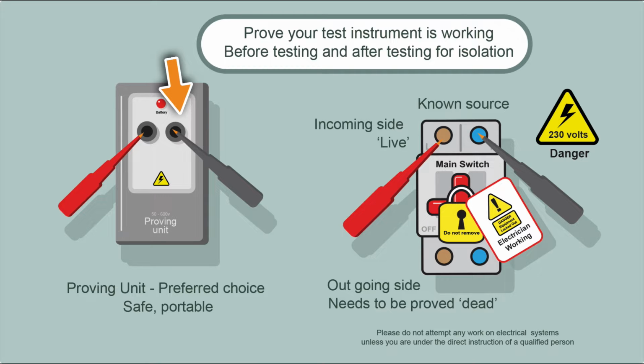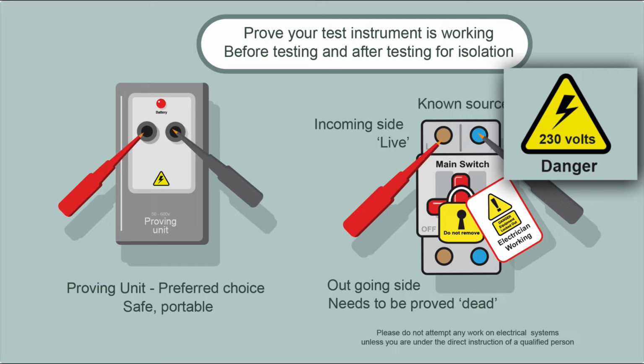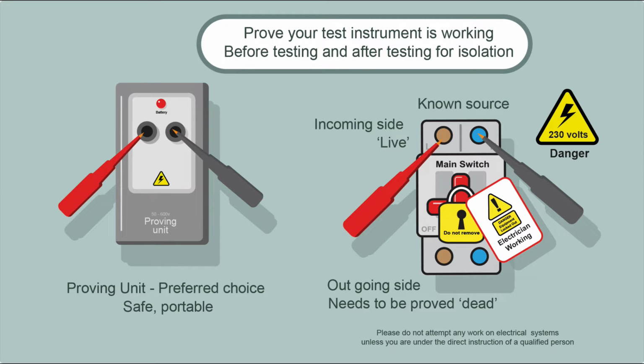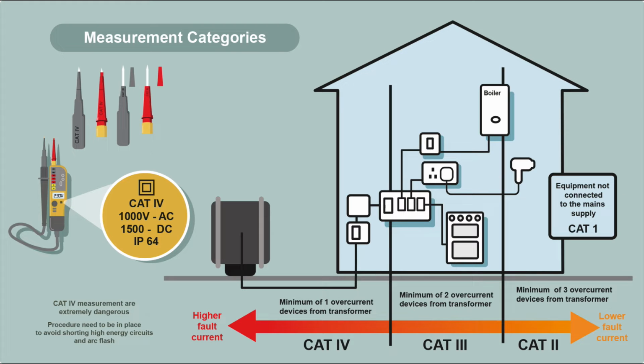You can also use a known source. That can be a bit tricky because as electricians you're called out because there's faults, so the supply might be faulty. But one of the recognised known sources is the incoming side of your main switch. Obviously that's a live test there. This is something you only do under the direct instruction of somebody who's qualified and when the system has been locked off and isolated.